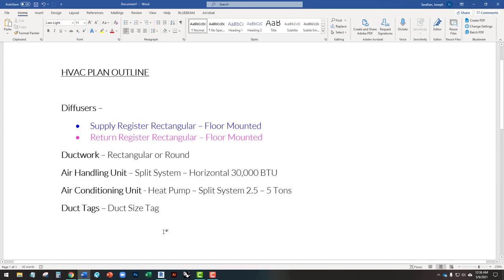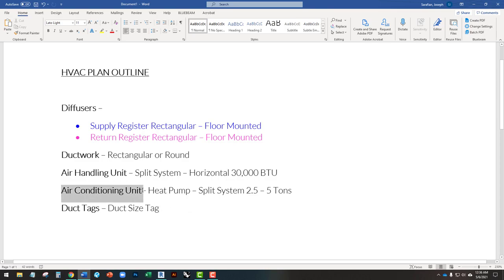We're going to have all of these elements in this model: diffusers, floor-mounted type. The ductwork is going to be all under the floor within the crawl space. The air handling unit is going to be a split system horizontal 30,000 BTU — for a small ADU. The air conditioning unit will be a heat pump split system 2.5 to 5 tons. We're going to use duct tags to tag all of our ductwork. This whole system will be under the crawl space, except for the AC unit which will be just outside.